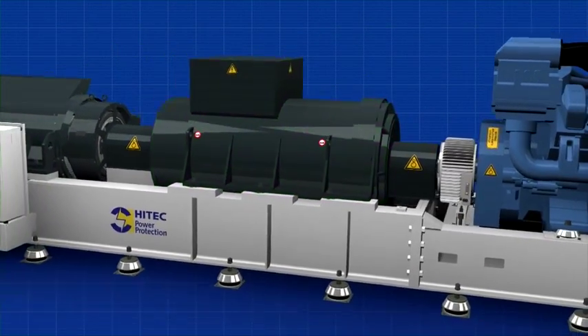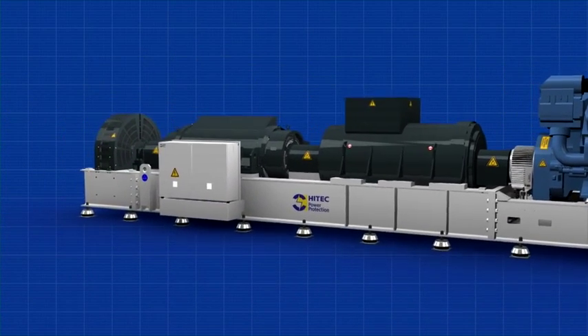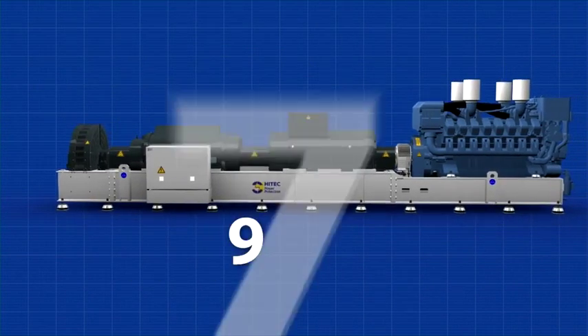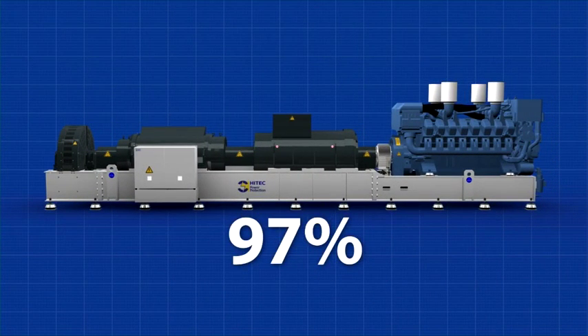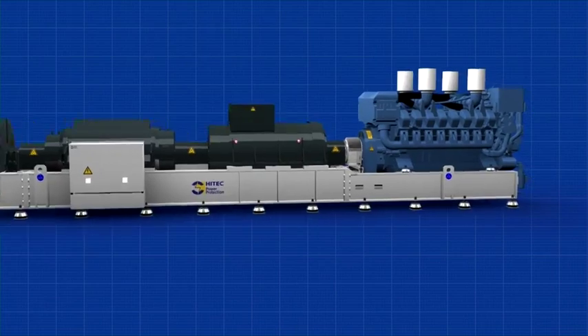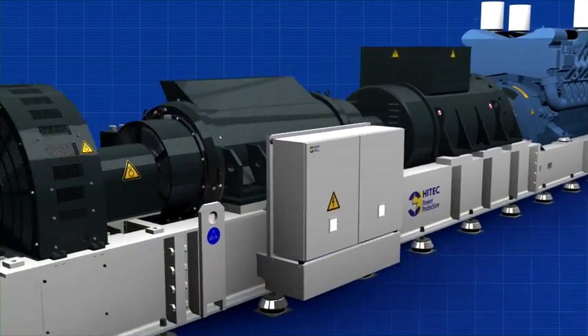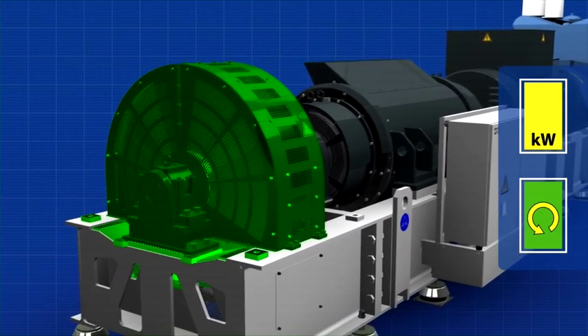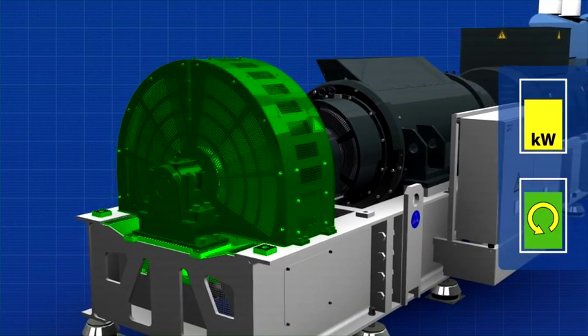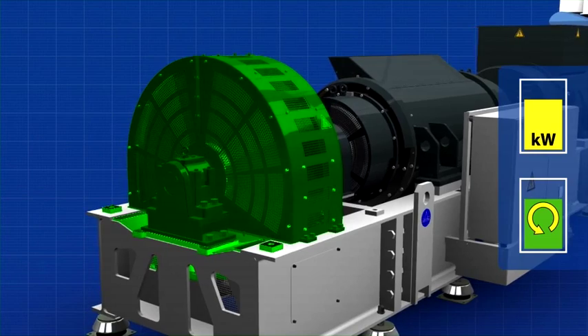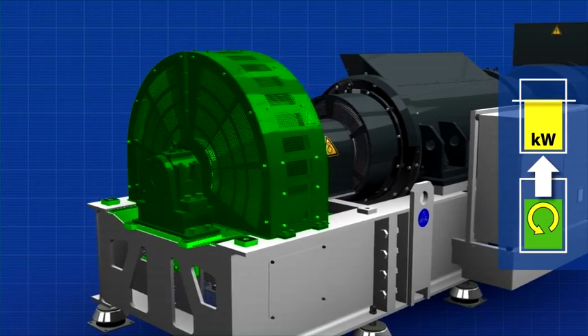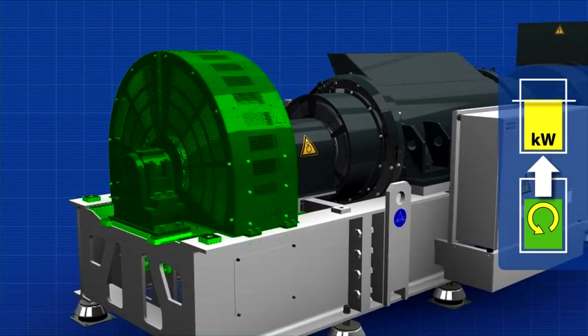Energy efficiency is fundamental to our design, and the HITEC UPS range has an end-to-end efficiency up to 97%. Utilizing HITEC's ESO mode, the energy stored in the flywheel is automatically controlled to match the load it is supplying. This significantly increases the overall system energy efficiency while still providing a full no-break supply to the data center's critical loads.